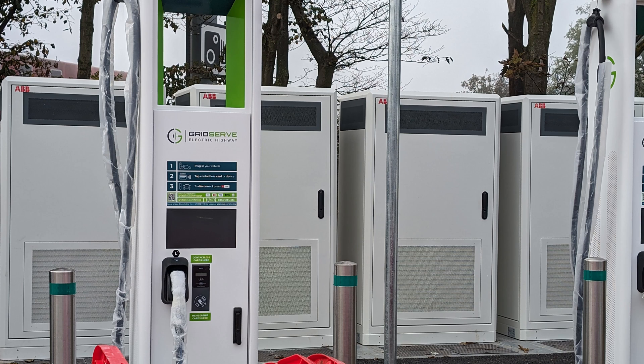These cabinets take in the 450 volt AC three-phase and first convert the AC into DC, which both the charger and the car use. These are called AC-DC converters — and they do just that. So now our electricity is in DC. It enters a voltage regulator. This device balances the input and the output so that when the load or the incoming power varies, the other doesn't — just like in your home, when you turn on a kettle the house lights don't dim. So when you plug in your EV the power remains constant. Conversely, if the incoming voltage drops or surges, the output doesn't. At this point we now have a stable voltage around 400 volts DC, carefully regulated, and that is fed through an underground cable to the charger.